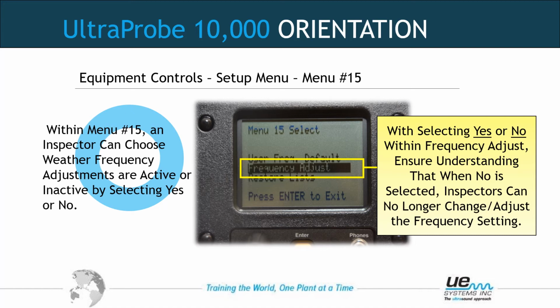So you go turn everything off except store record and record wave in the function bar menus, because you know the back way into the gun now. You come into here and turn frequency adjust off. So the gun is presetting itself to the sensitivity and frequency it was at as the baseline. So your trend is still good because they can't change the frequency as long as they're taking a decent reading. You're good to go. Other than that, I would imagine your frequency adjust would be turned on all the time, and then the yes option.